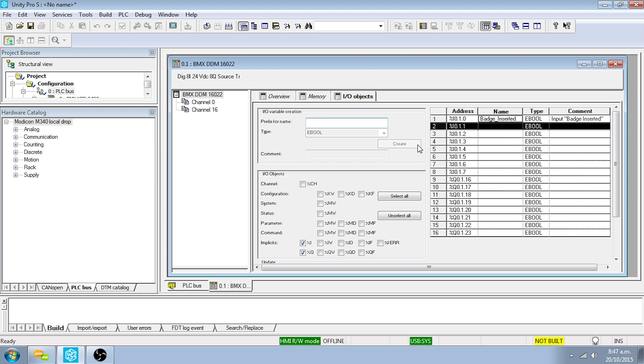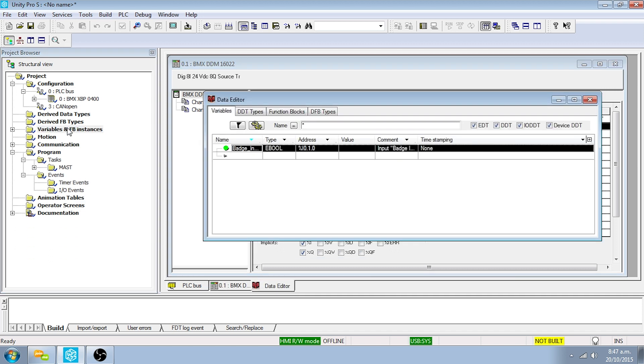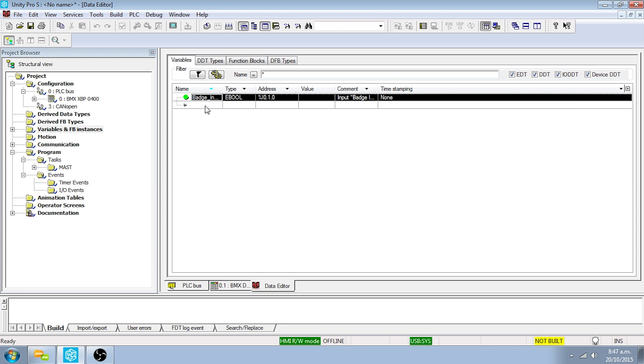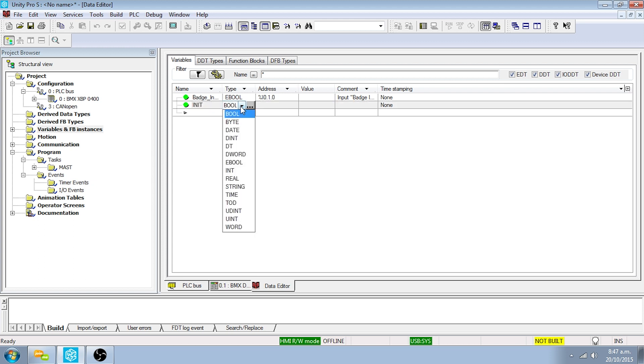The variables for this application can be entered one at a time manually, or alternatively imported from an XSY file. For the purposes of this demonstration we will import them from the project files. Before importing, the first variable needs to be manually declared. Double-click on the Variables and FB Instances directory in the project browser, select the first available line, enter 'init' in the name field, select BOOL in the type field, and enter 'sets the Grafcet to the init step' in the comment field.